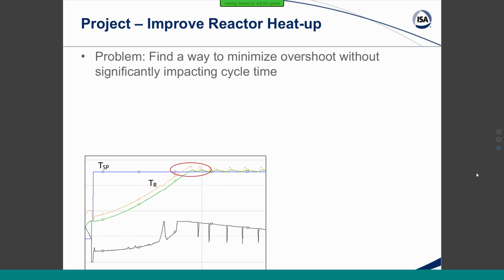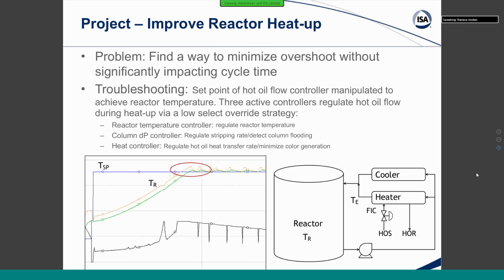Some of them are what you would probably consider to be just an hour or two's worth of work. But I thought I'd include some of those as well, just for learning purposes. So this one here, we were trying to improve our reactor heat up. We had just installed a brand new super high powered hot oil unit, and with this new hot oil unit, we were actually overshooting our temperature set point pretty significantly. And this was causing some quality issues that we had to rework. So we were looking for a way to minimize that overshoot without impacting our cycle time.